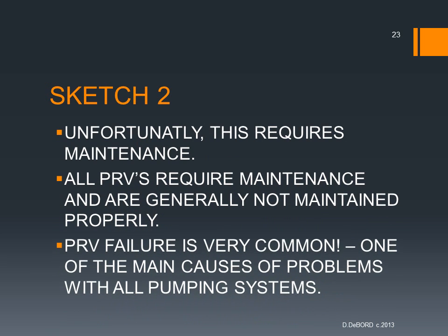Problem is, these valves require maintenance. All PRVs require maintenance and are generally not maintained properly. Again, make sure the contractor actually put in the remote sensor, because that can be an option on the valves, and they might try to, let's just say they forgot to put it in. I'm not saying they would do it on purpose. PRV failure is very common. It's one of the main causes of problems with all pumping systems, not just hot water recirculating, but domestic pumping systems also.